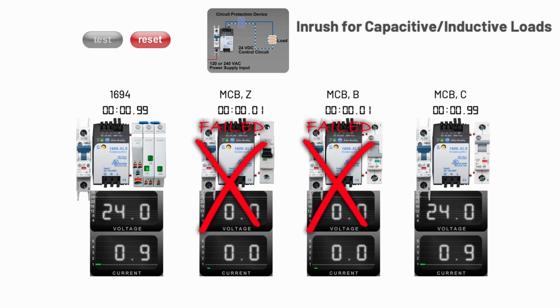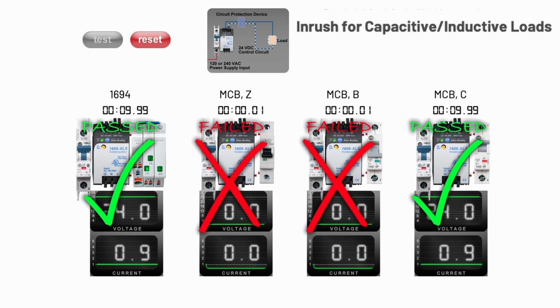And in this last example, we're able to see how the 1694's smart device design allows for the high level of short-term inrush current that's required for capacitive charging loads and inductive loads like small servo motors. Only one of the 3 miniature circuit breakers passed the test because they aren't able to differentiate between it being an inrush current or a short circuit.